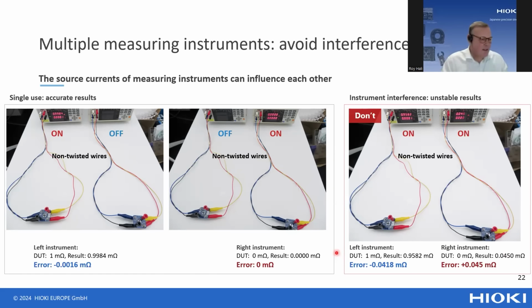That's because the test current flowing in, for instance, the right instrument interferes with the sense wires of the other instrument, inducing another voltage on the sense wire and creating unstable and inaccurate measurement results.